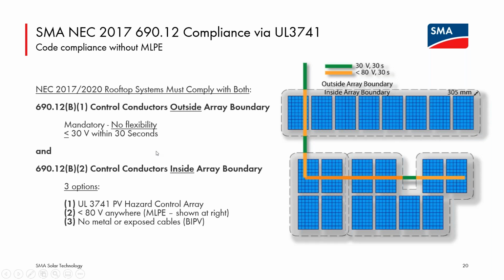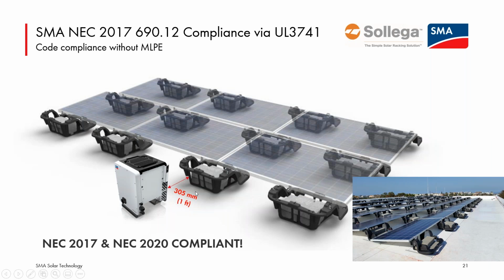So that will cover all of the conductors outside of the array boundary, which are still required to go down to very low voltage. And then the UL 3741 listing, without the need of any module level power electronics, will satisfy the inside of the array boundary, again, as 2017 or 2020 NEC specifies. So certainly for commercial rooftop systems in the US, where we generally had to fall back on this voltage reduction, this is a very exciting, I think, additional option.